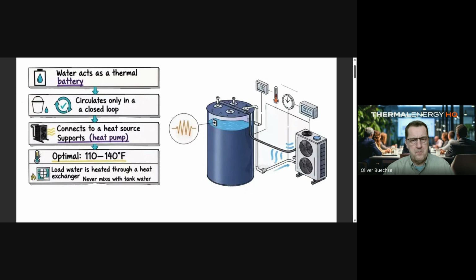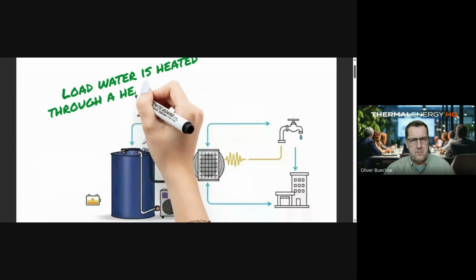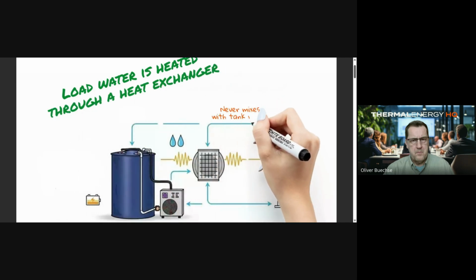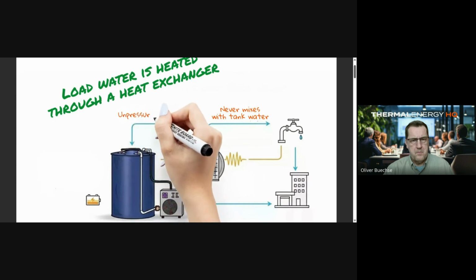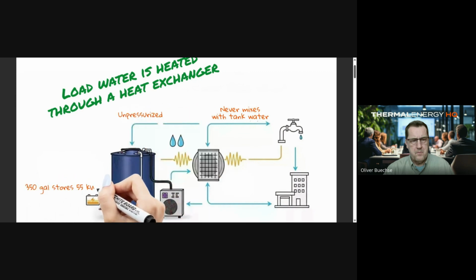The optimal tank temperature is between 110 to 140 degrees Fahrenheit, but higher temps up to 180 degrees Fahrenheit can also be supported. The usage water on the load side is heated via a heat exchanger and never mixes with the tank water. The tank is unpressurized and can hold 55 kilowatt hours in the 350-gallon version.